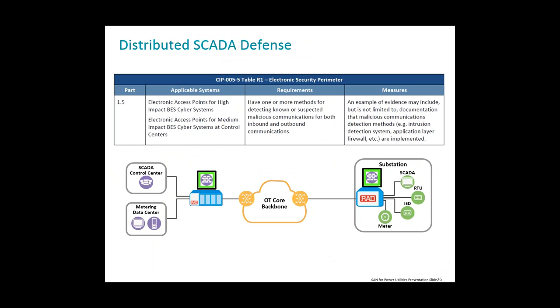We'll talk a bit about SCADA and the requirement in NERC CIP—specifically CIP 005-5. What it says is, for the applicable system, if you have an electronic access point for a high impact cyber system, or an electronic access point for a medium impact cyber system at a control center, then you have to have one or more methods of detecting known or suspected malicious communications. The measures listed as evidence may include documentation of malicious communication detection methods—in other words, intrusion detection systems, application layer firewalls, etc.—being implemented. So NERC is saying that these defined systems are required to have some method of malicious communications detection, such as application layer firewalls. That's a requirement going forward.